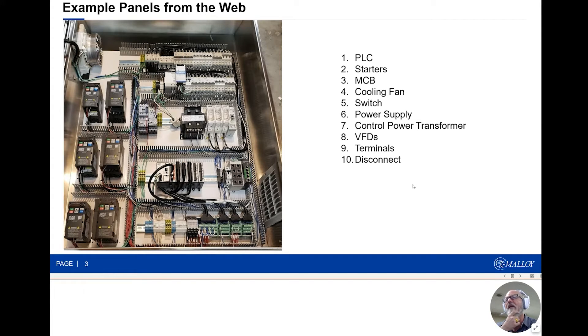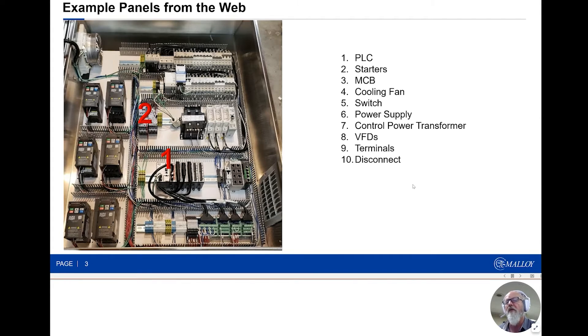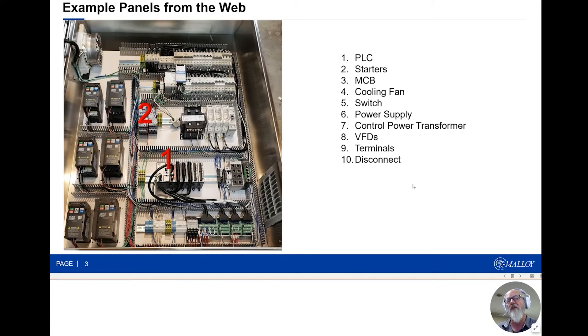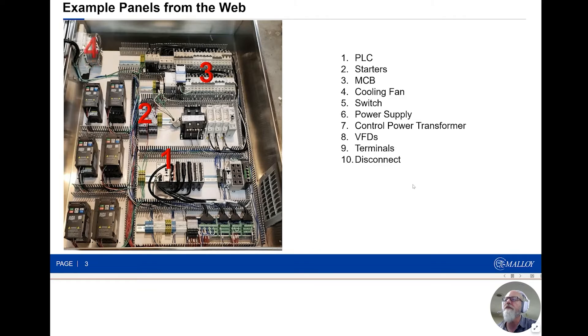The next one is a little more densely designed. Again, number one is the PLC — this is an Automation Direct design, so you'll see many different components than the first example. Then we have starters. Starters have two specific designs: one is traditional, where you have a contactor with an overload relay below it. The more modern combination design has a motor starter protector (MSP) on top of the contactor, which emulates the short-circuit protection of a traditional molded-case circuit breaker. Under Article 430, you can get a group motor rating so you don't have to use fuses. Then we have miniature circuit breakers, a cooling system, fans, and vents visible on the left and right-hand sides.